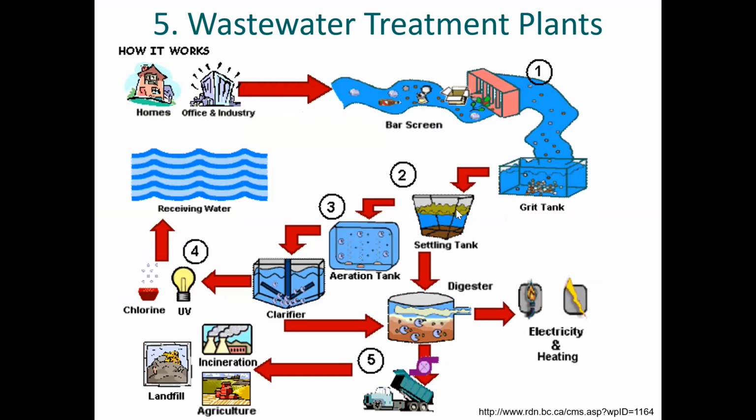And at our wastewater treatment plant, they inject some air into the system at this point, and it causes some of these things to float, and they can skim it off. And that's actually usually one of the first things that we see at that point. Step 3, they're adding the oxygen and encouraging the microorganisms to grow. You can see there's some clarifiers in there allowing them to settle. And you can see we've got our later steps where we're adding UV. Chlorine, like I said, isn't that common because then we're polluting the water, and then it's going back to the river. Over here, we've got some more solids and other digestion going on.